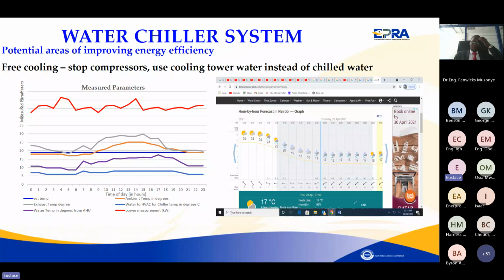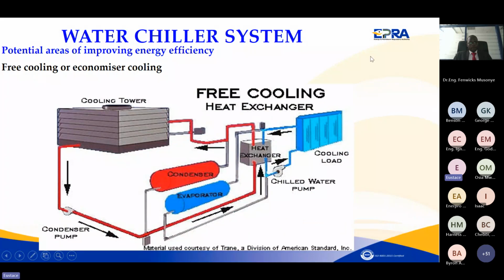There is free cooling. Once you identify low temperatures, especially at night, you can introduce free cooling. All this we have talked about during our presentations. You can also bypass, like we said in the chiller system. If you find that the ambient temperatures are relatively low, you can bypass and use the cooling tower directly instead of using the chiller to cool the system.